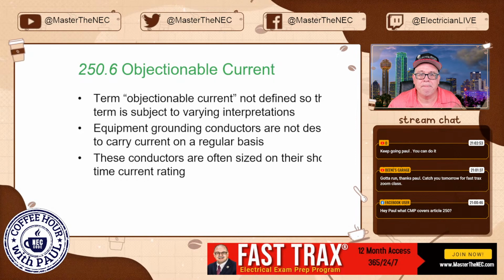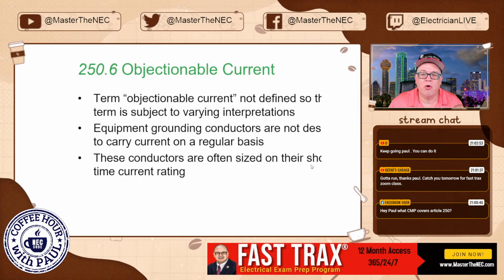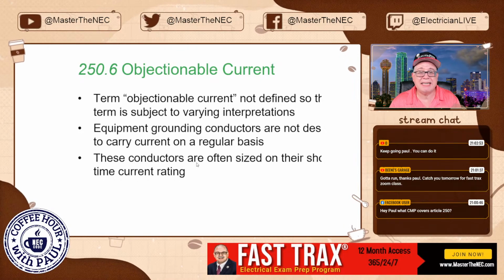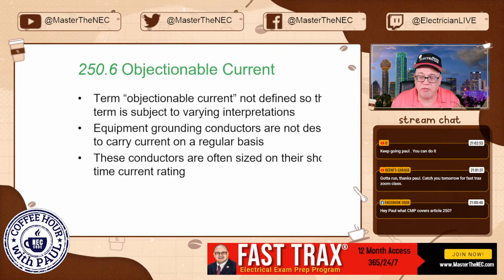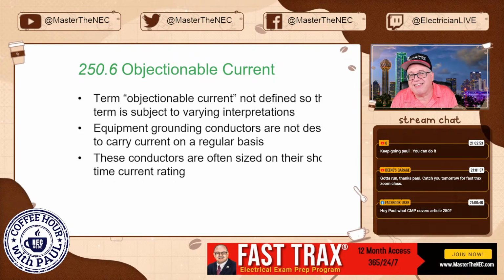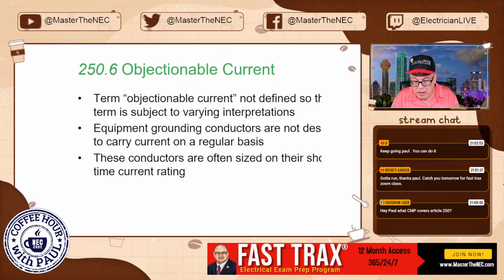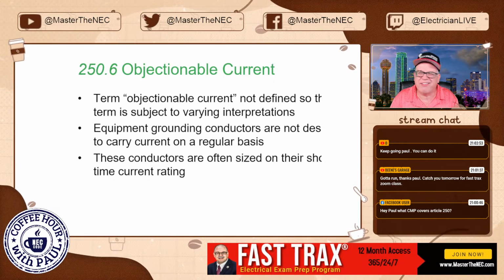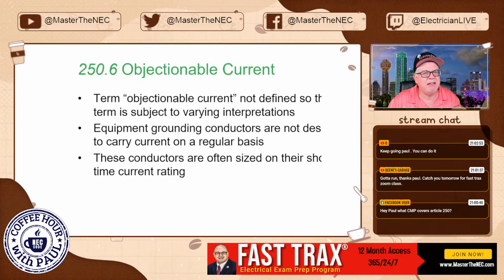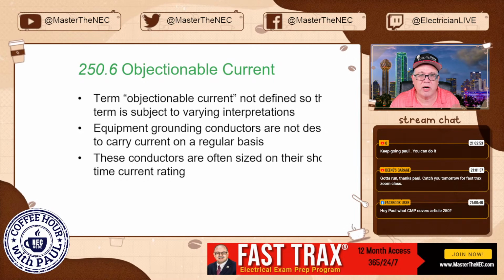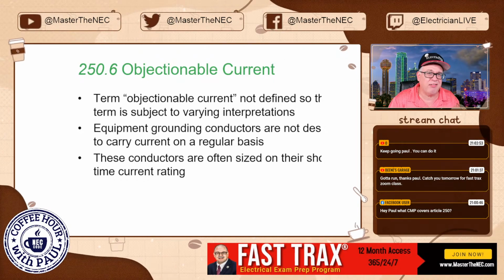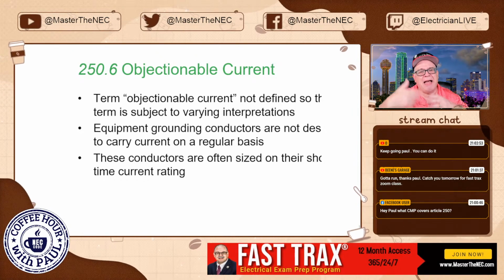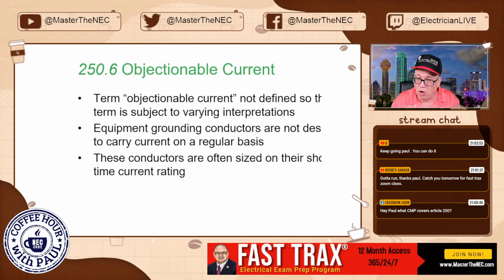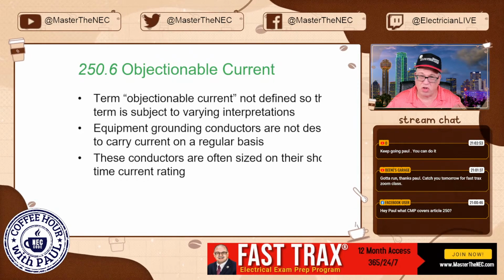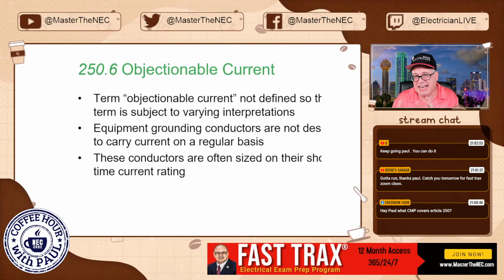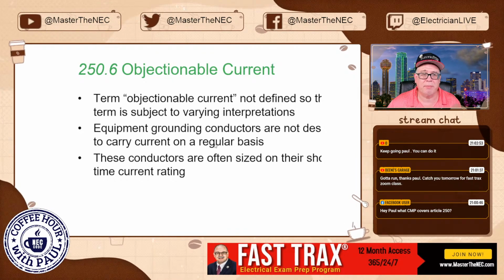Now, it says these conductors are often sized on their short time current rating, but I can tell you right now that equipment grounding conductors are sized based on the overcurrent protective device. Inherently, overcurrent protective devices usually operate or trip at 6 to 7 times their rating, depending on what you're dealing with. So a 20 amp overcurrent device, typically 20 times 6 or 20 times 7, depending on the manufacturer. It takes that much current to trip it. Well, if you provide this low impedance path properly, you're not going to have any time issue, because we're talking about thousands of amps instantaneously. So, not going to be an issue.